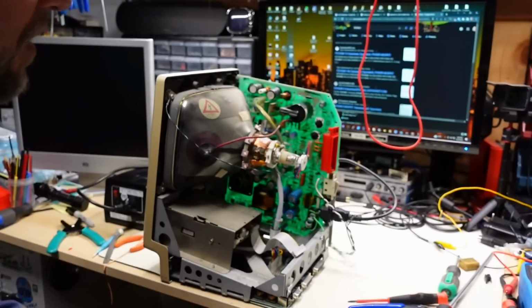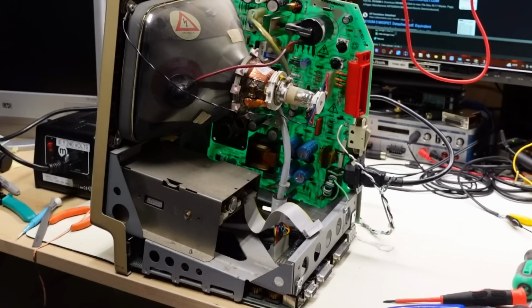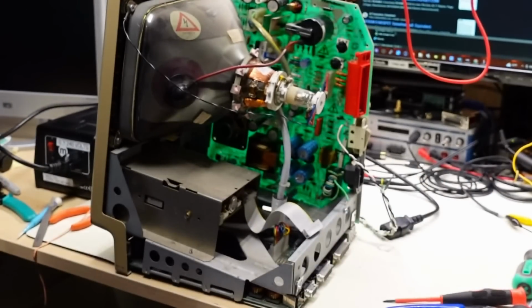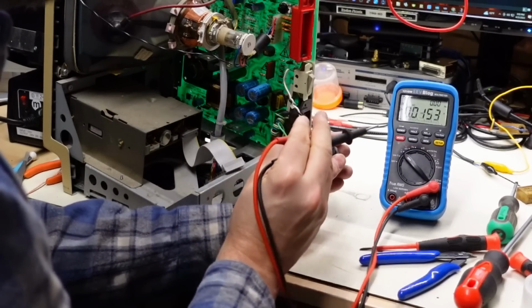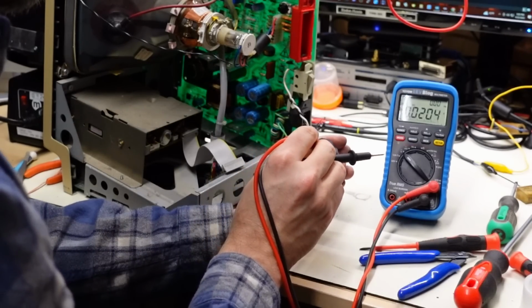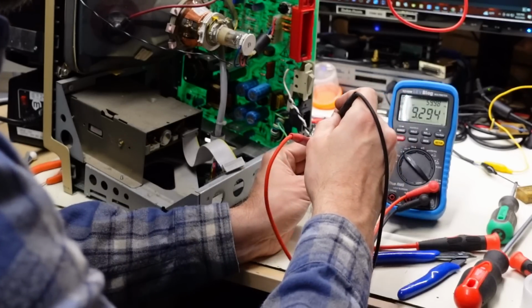No, it just tripped the breaker again. It's really weird too, because the step-up transformer is off right now. So why exactly is this tripping the breaker? I'm wondering if the switch on there is switching the neutral and not the hot.